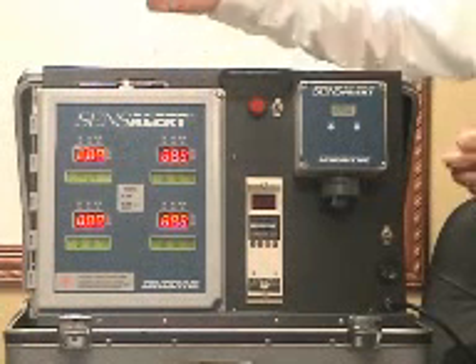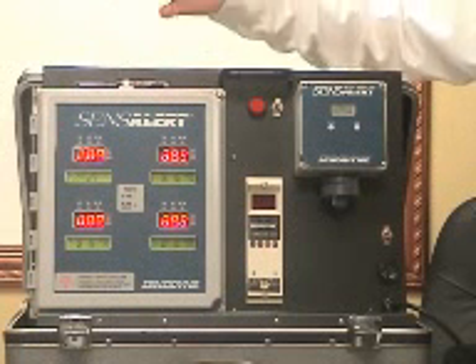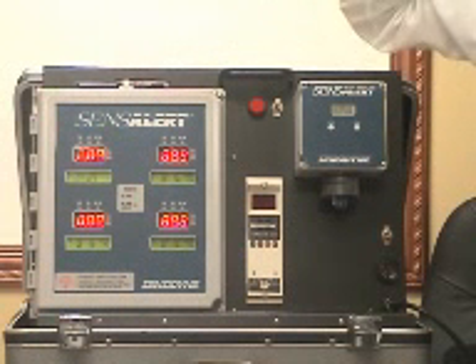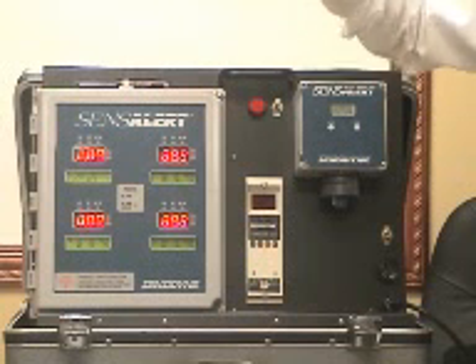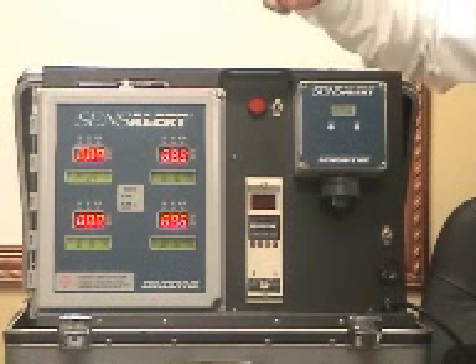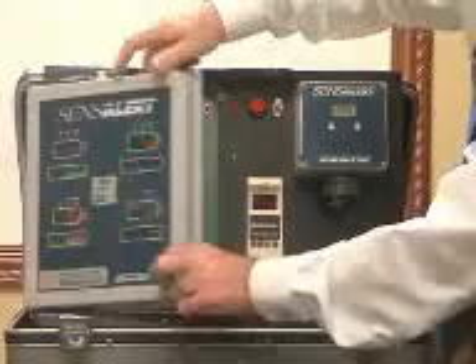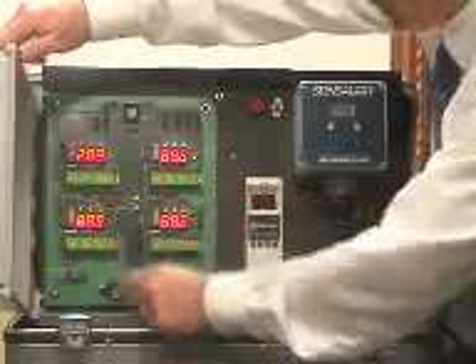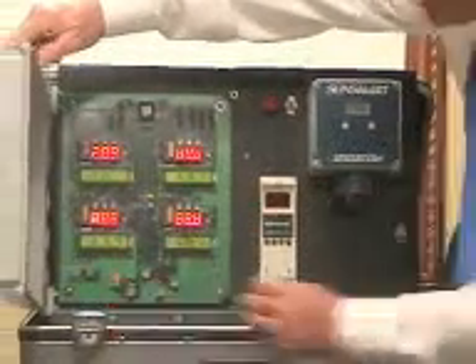For instance, if the customer stored oxygen in his facility, in tanks, you don't want a leak of oxygen because it's expensive, plus it's an accelerant to combustion. So what we'll do is just show you, right now it's showing the alarm set point. We'll go back to normal operation by hitting next.